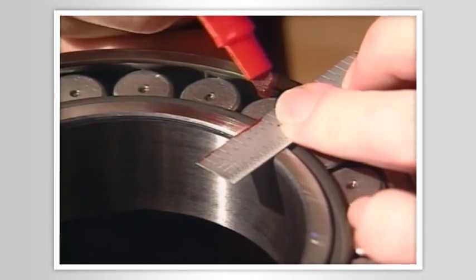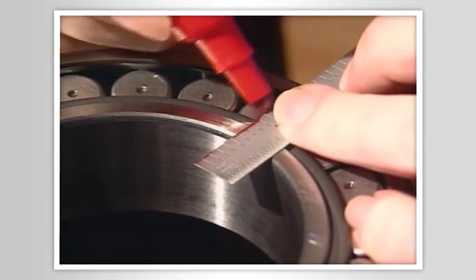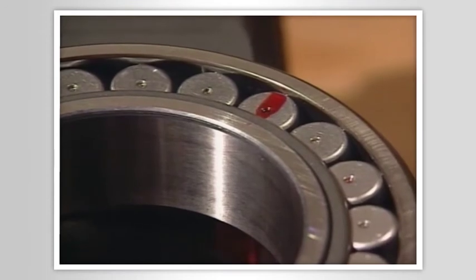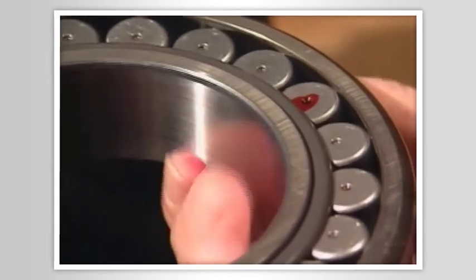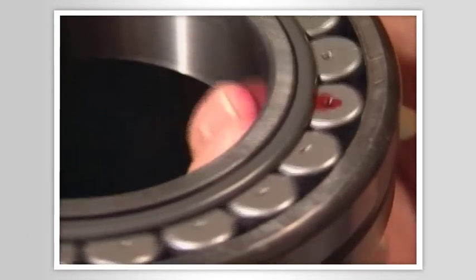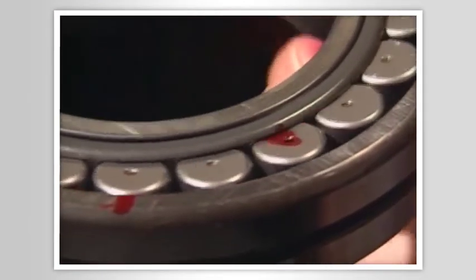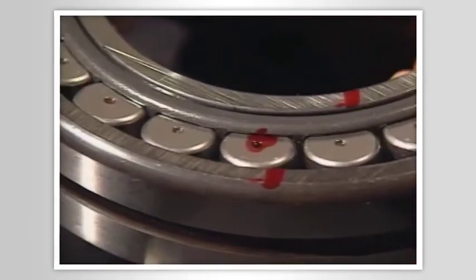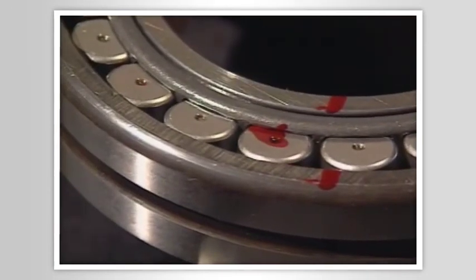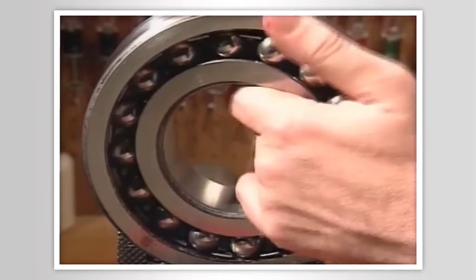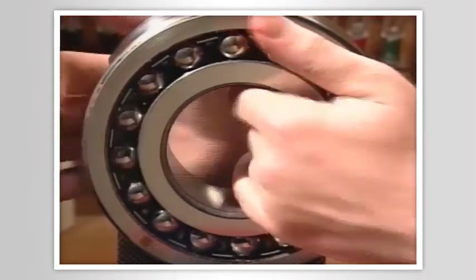Now let's draw a mark through the center of a rolling element. This time we'll count the number of times it spins in one rotation of the shaft. 1, 2, 3, and part of another. In the manufacturer's literature, we find a ball spin frequency multiplier of 3.73. If there is a defect in one or more of the rolling elements, a fault frequency will be generated at 3.73 times shaft speed.